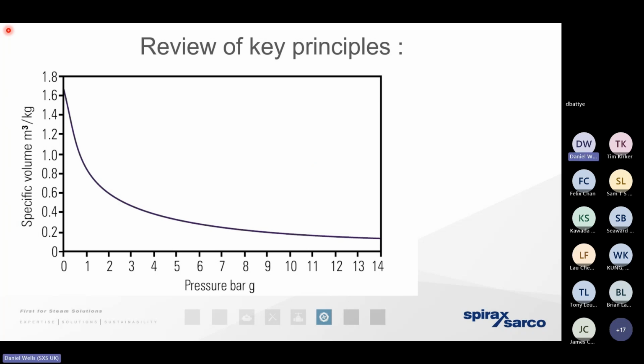Water as a liquid is a single phase, non-compressible liquid. So a kilogram of water is 0.001 cubic meters. It boils off to give us steam as a gas, and it's expanded by 1600 times. So that's one of the reasons why we like to generate steam at a high pressure. High pressure, small volume, a lot of motive energy to move the steam around the infrastructure. But crucially, because of the high pressure and small volume, we've got a small, cost-effective infrastructure, which is useful, especially when we're moving that steam thousands of meters around site.